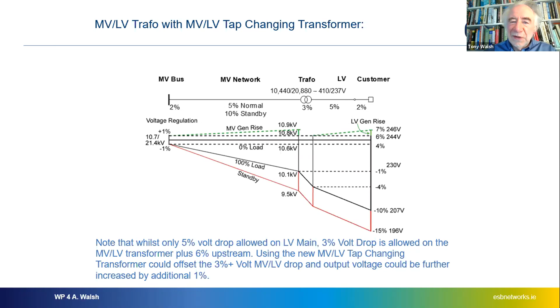And here's a normal transformer with multiple windings, but with the tap changer added onto the top. This is an electromechanical device made in Germany, quite expensive because they're new, and it basically nearly doubles the cost of the transformer. So we only use it on larger transformers, such as a 1 MVA transformer. But having a 1 MVA transformer with the tap changer means it will not only cope with overloaded situations, it'll cope with overloaded situations where we have voltage as an issue.